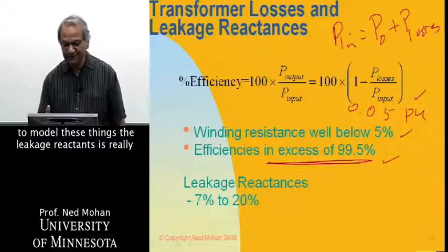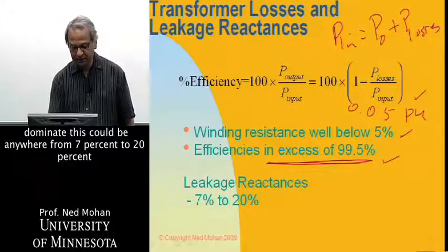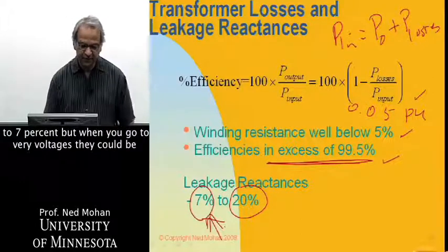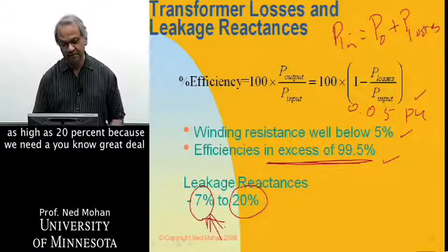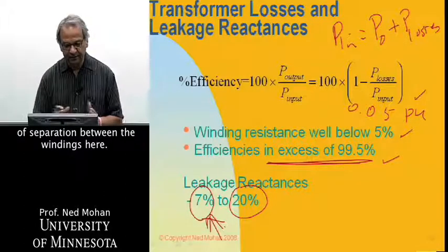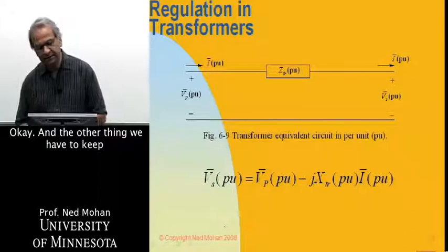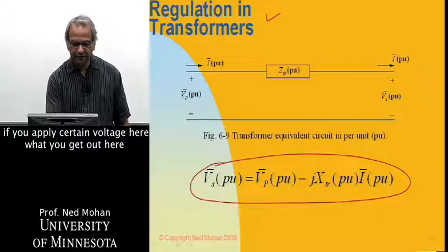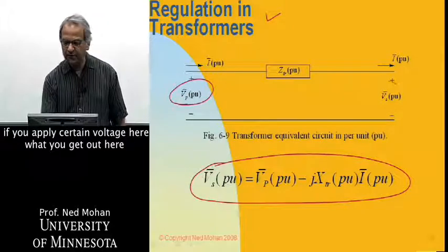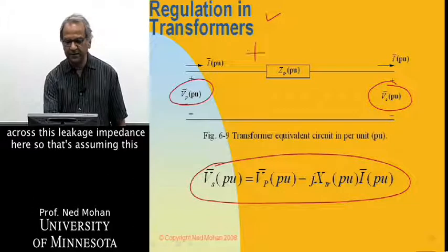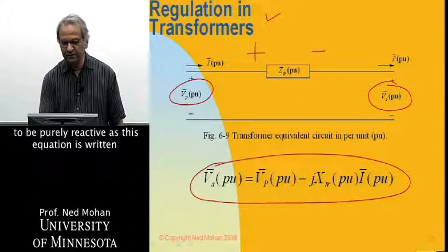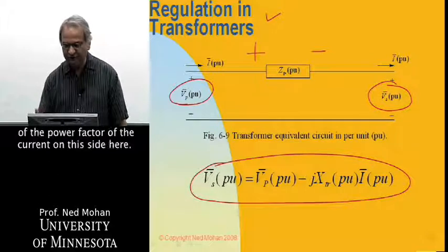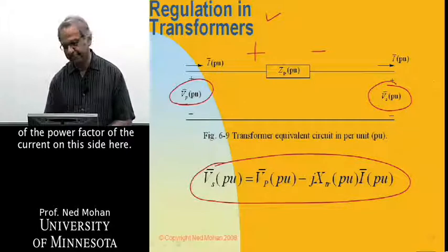So, when we go to model these things, the leakage reactance is really dominant, which could be anywhere from 7% to 20%. So, at low voltages, low voltage transformers, they are close to 7%, but when you go to very high voltages, they could be as high as 20%, because we need a great deal of separation between the windings here. And the other thing we have to keep in mind is something called regulation in these transformers, and that is given by this equation, as you'll expect. You know, if you apply certain voltage here, what you get out here in per unit is not the same because of the drop across this leakage impedance here. So, assuming this to be purely reactive, this equation is written, and you can see that this drop is a function of the power factor of the current drawn on this side here.